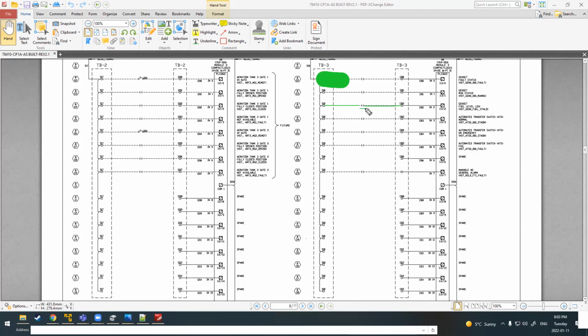This indicator is a generic contact, and it will show up in ladder logic. So that is what you would see for a normally open contact of anything, whether it's a relay, whether it's a switch. It's a generic normally open, and when we get into the programming, we'll see that as a normally open or examine if closed. Here, this is a switch. That's your hand-off-auto switch over here.